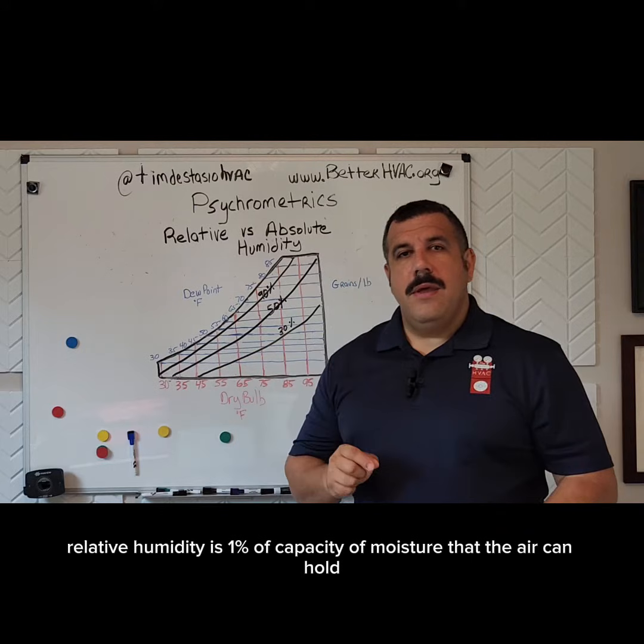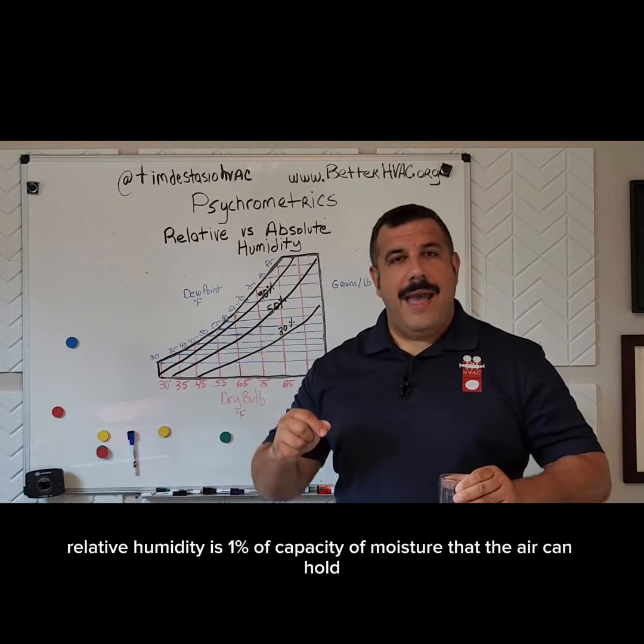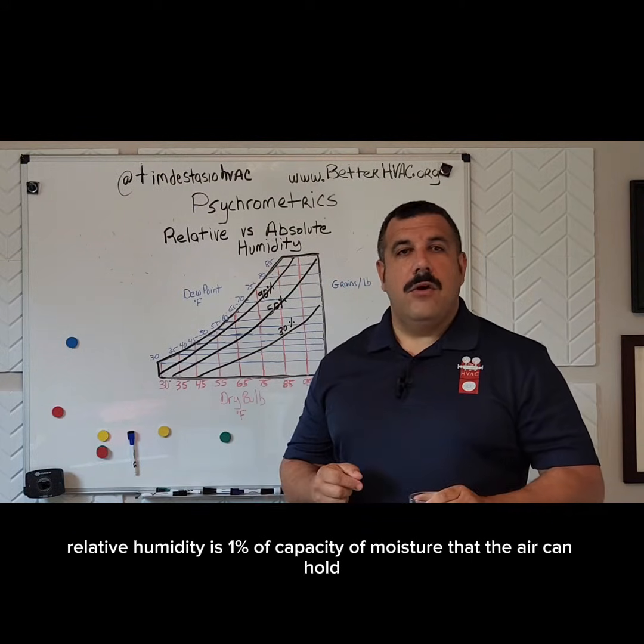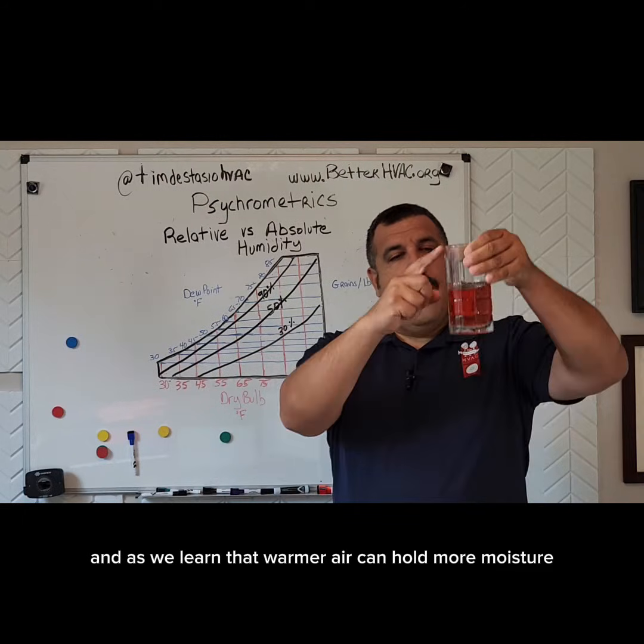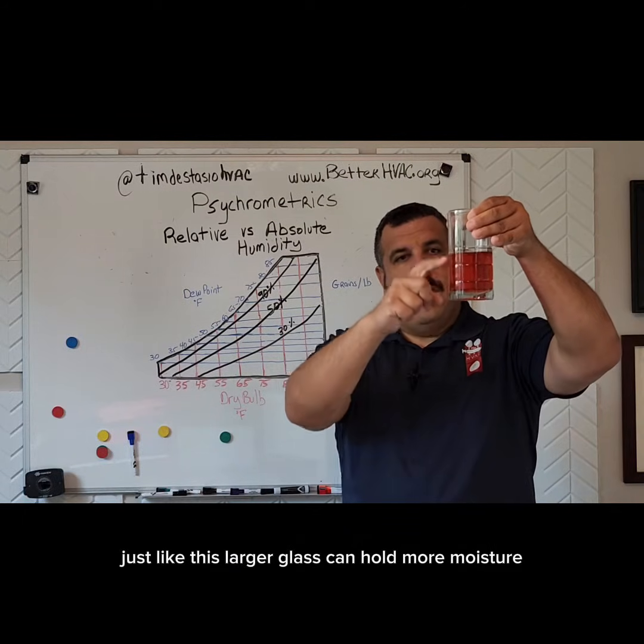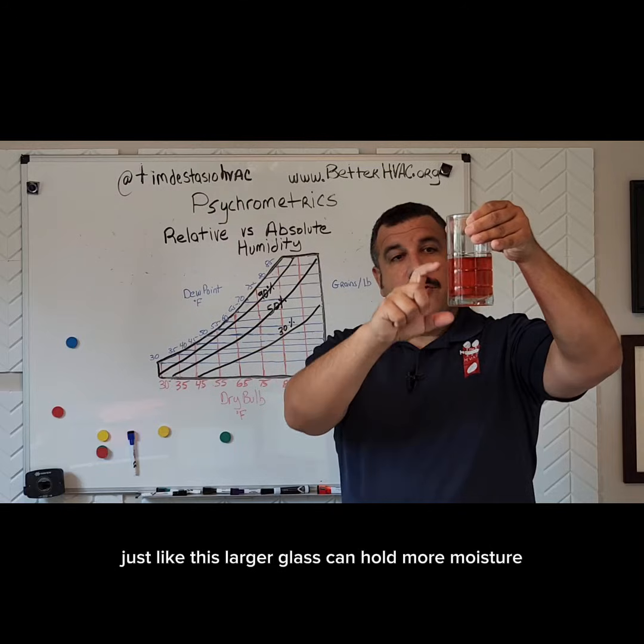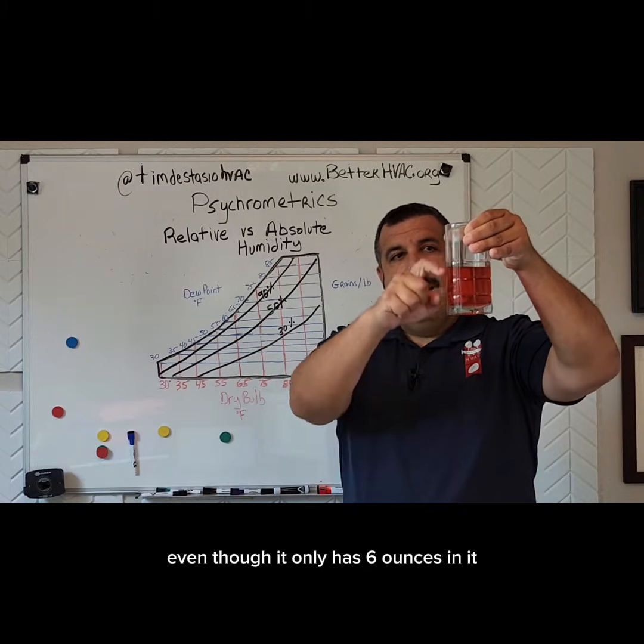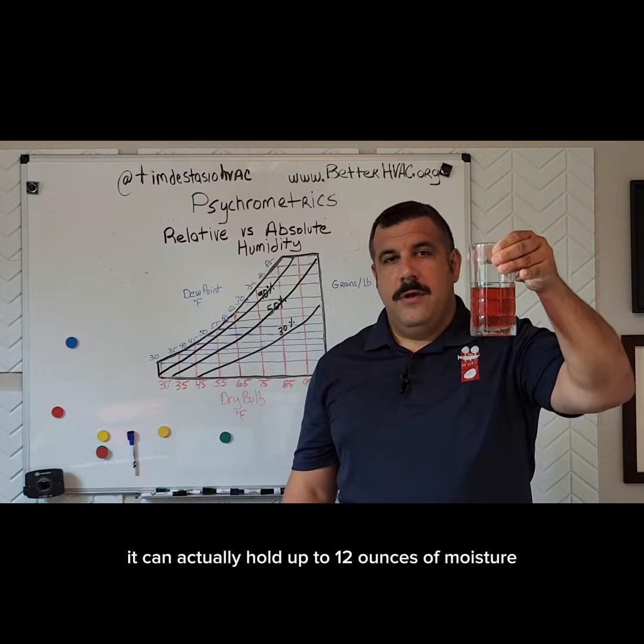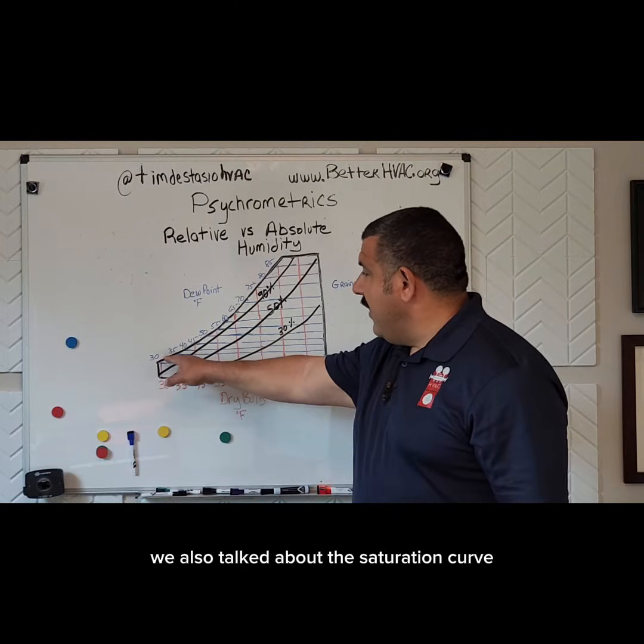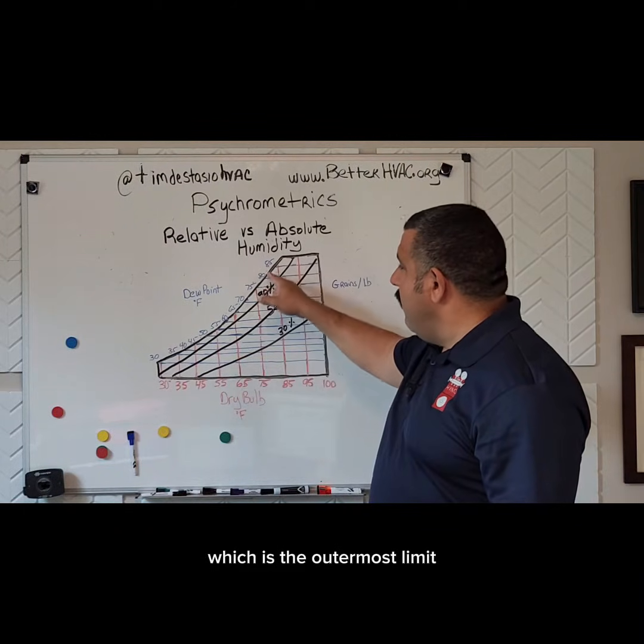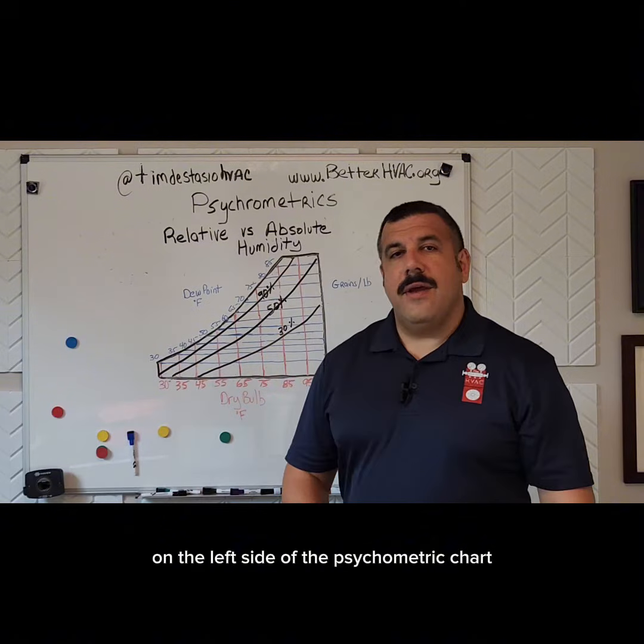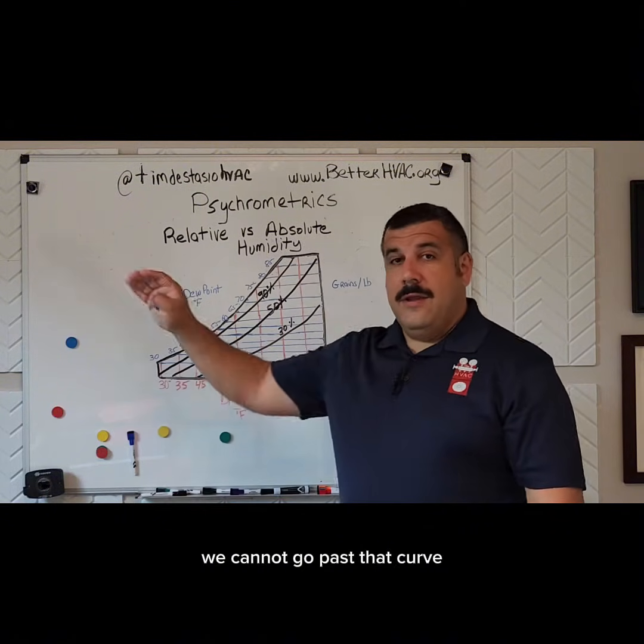However, relative humidity is a percent of capacity of moisture that the air can hold. And as we learn, warmer air can hold more moisture, just like this larger glass can hold more moisture. Even though it only has 6 ounces in it, it can actually hold up to 12 ounces of moisture. We also talked about the saturation curve, which is the outermost limit on the left side of the psychrometric chart. We cannot go past that curve.